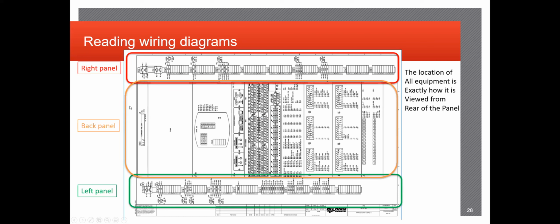Looking at these, you can see usually the wiring, I would say 99 times out of 100, would be viewing the panel from the rear side, and identifying which side for which terminal blocks would be associated with it, whether it be the right or the left, and all the equipment in the back side of the panel.